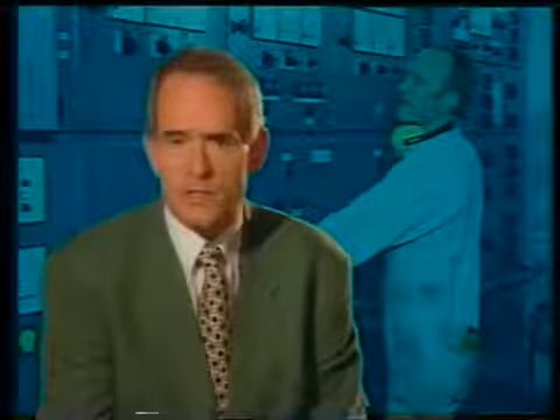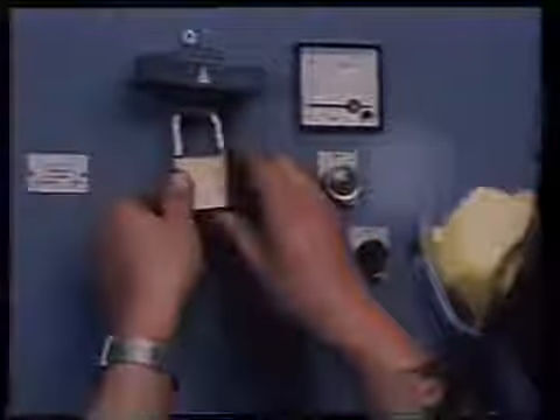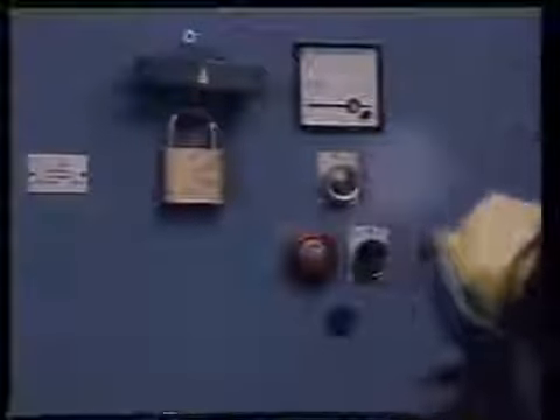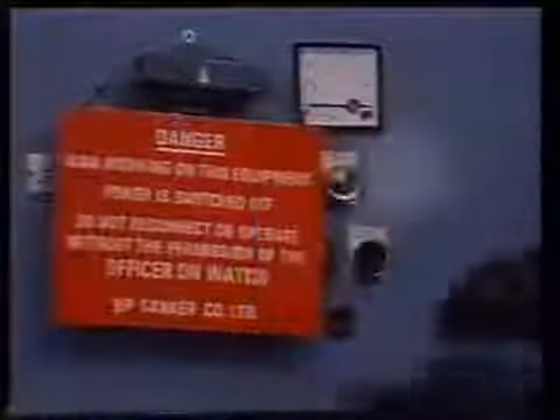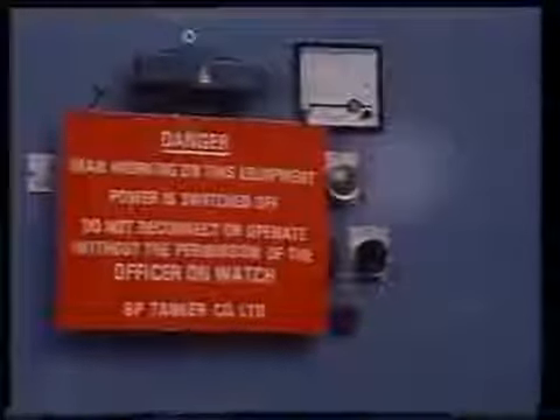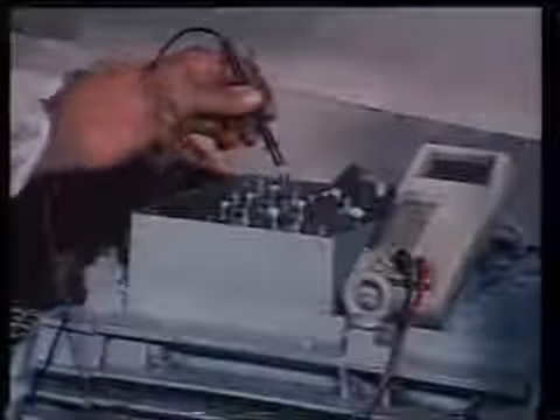Now we must emphasize electrical safety. The golden rule is, before any work is done on an electrical installation, first isolate the circuit by removing the supply fuses or locking the circuit breaker in the open position, so that the circuit cannot be energized accidentally. Then post a warning sign to alert others that the circuit is being worked on. Then prove the circuit dead with a voltmeter or an approved line tester.